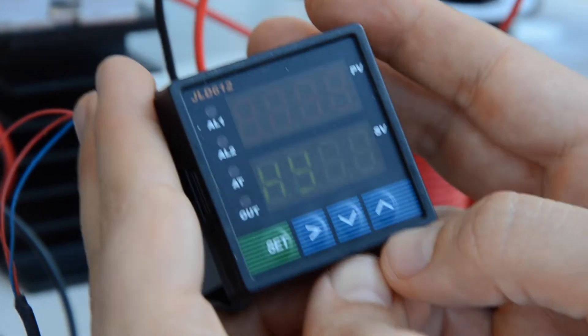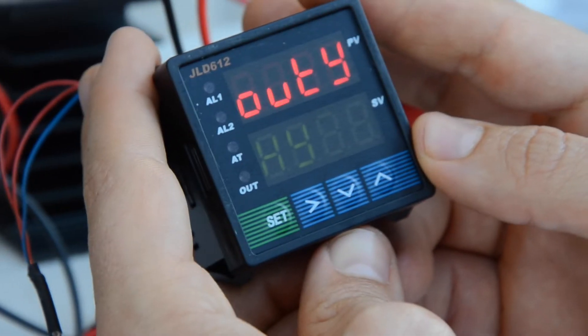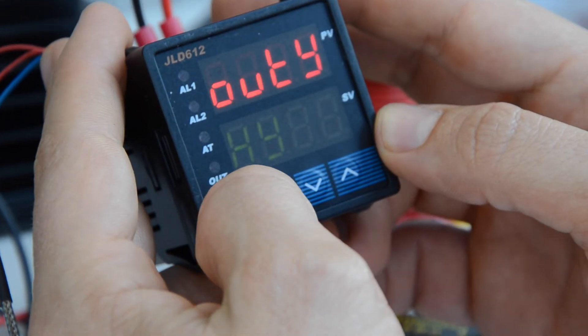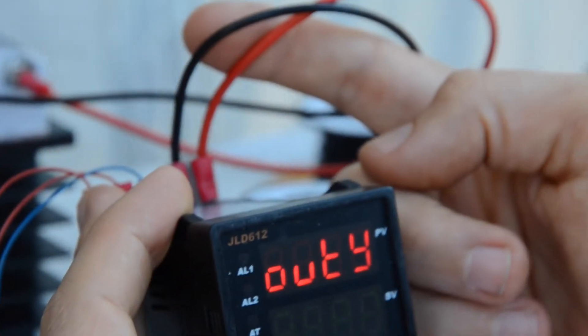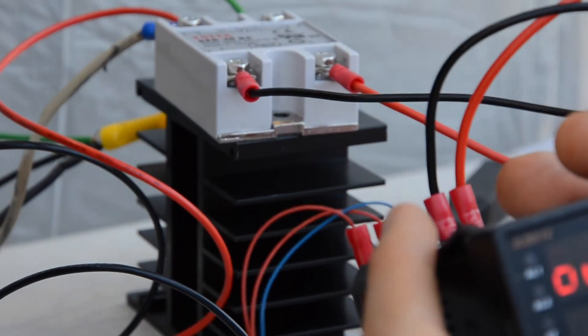So we'll set that one and we'll scroll up to O-U-T-Y. This is the relay method that we're using and it has three settings. The one that we want, 0, 1, and 2, we want 2 which is what uses the solid state relay. The other two are a different setting that doesn't work for our system.